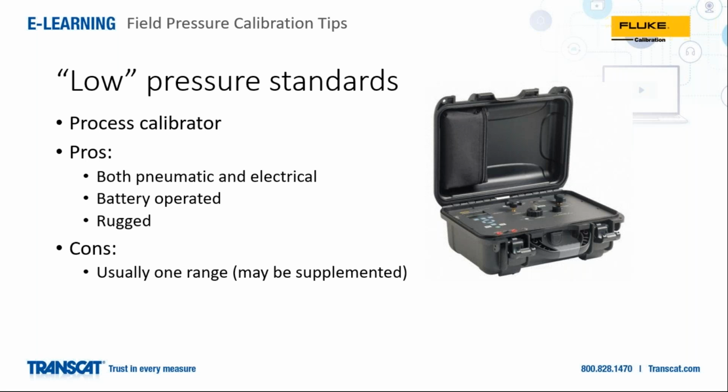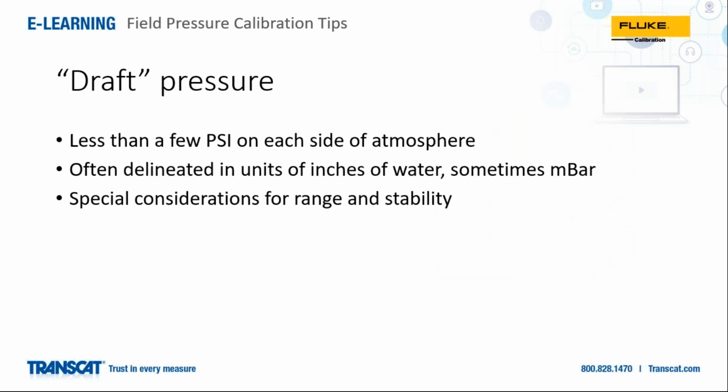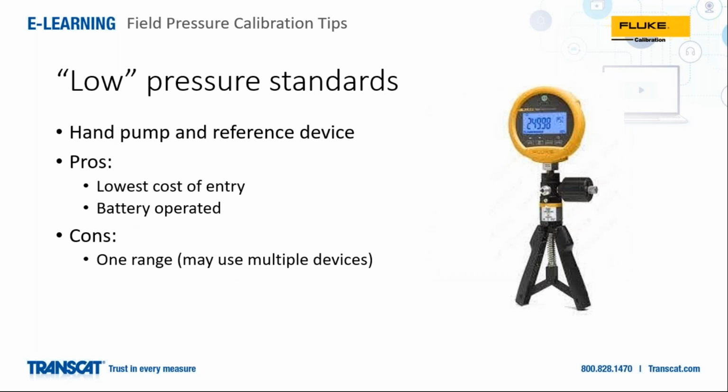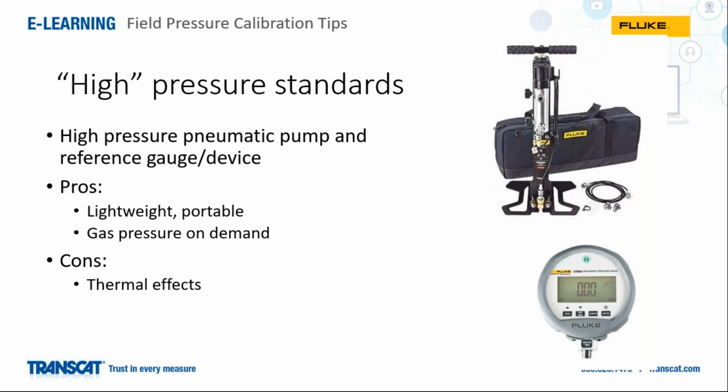Okay, which calibration standards do you typically use? Is there an ANSI or NIST calibration procedure that can be used? There is not really a standard calibration procedure for any given thing. Unfortunately, or fortunately, depending on how you want to look at it, there's not a good document that you can point to that says here is how you calibrate every pressure device out there in the world.